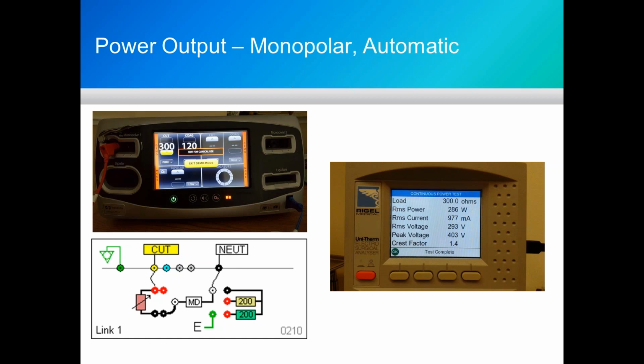Below that is a connection diagram that is on the side of our analyzer, and this shows up on the display when you're about ready to do a test if you choose to show the diagram. And it just shows basically what we had in that earlier photo with the external power resistor, the external current transformer and such. We're coming from the active output port of the monopolar output. We're showing cut, but cut and coag come out of the same port on this unit. And we're going to the top end of a variable resistor bank, which is set for 300 ohms, which is what they specify for a test for cut. For the actual coag, we'll be using 500 ohms of course. Through the MD measuring device, which is in fact our internal current transformer. So we are actively measuring RMS current, and then back to the patient return.